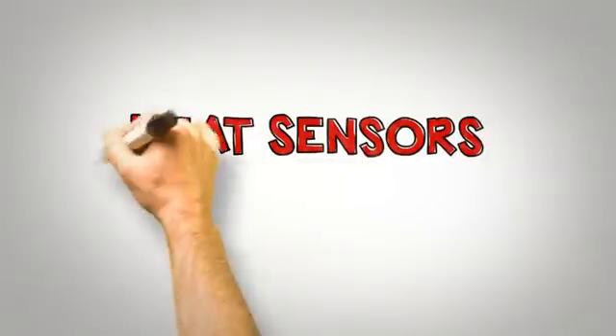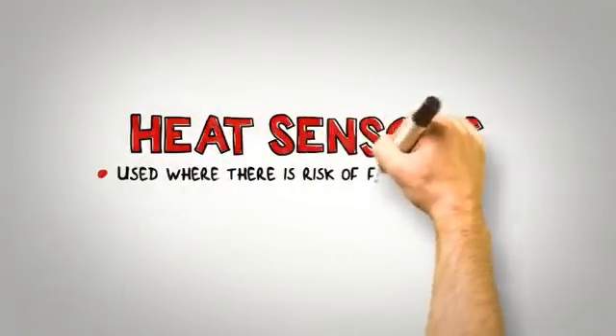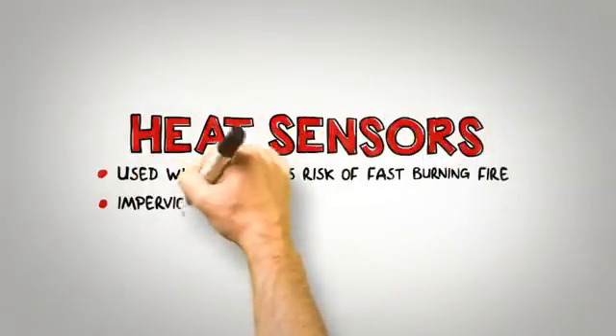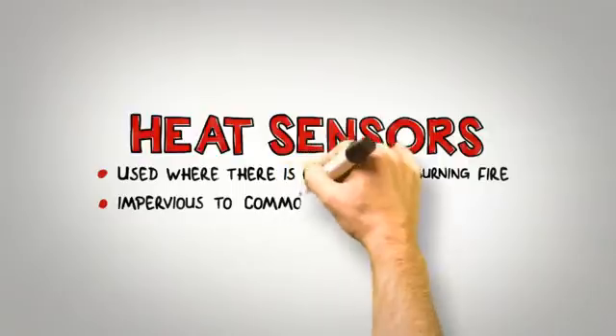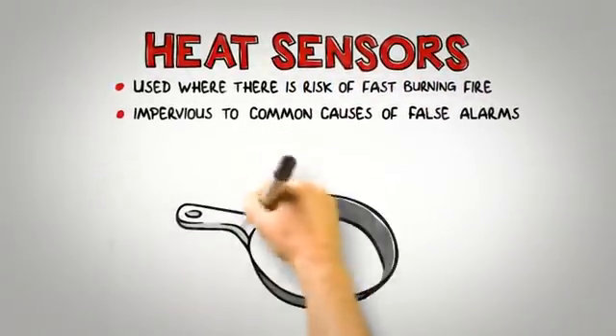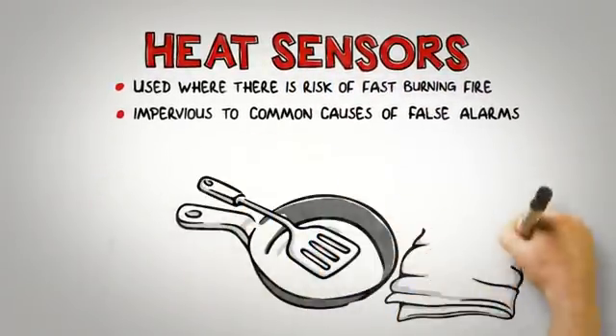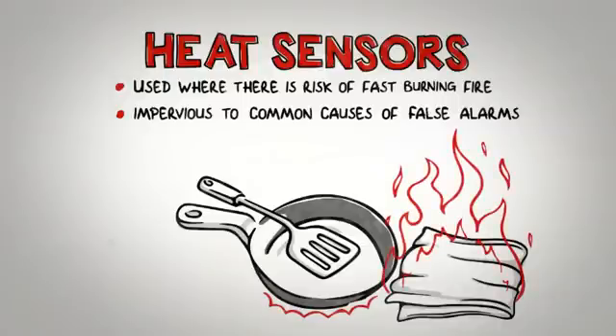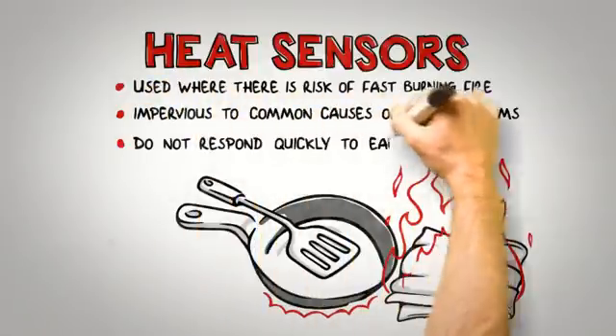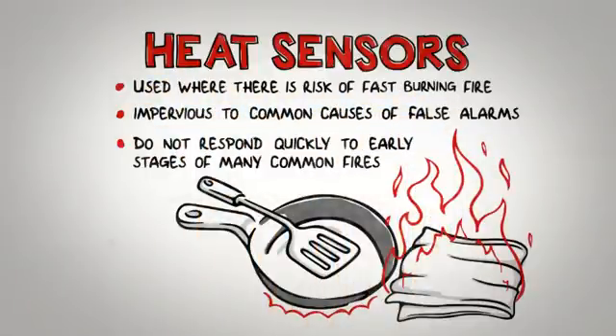Heat sensors are used in environments where there is a risk of a fast burning fire. These devices are virtually impervious to the most common causes of false alarms and are primarily used in areas such as restaurant kitchens. The reason they aren't used throughout a building is because they do not respond quickly to the early stages of many common fires.